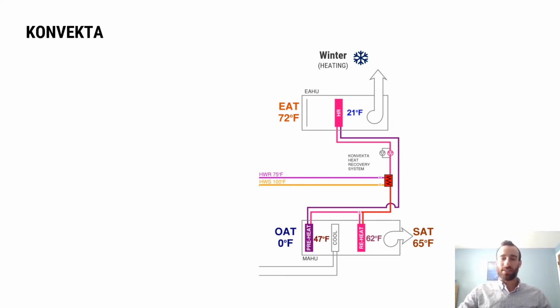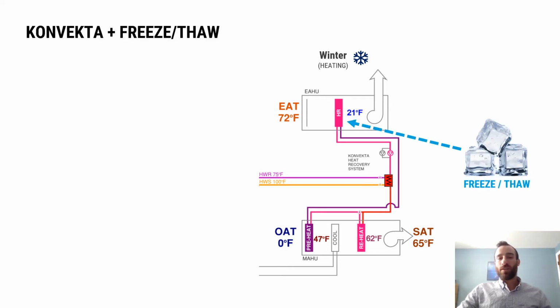recovery system. So this is an example of KONVEKTA, which is a glycol energy recovery system, probably the most efficient one on the market available today. One of the issues that plagues glycol energy recovery systems is that if you cool the exhaust too much, if you extract too much energy from the exhaust airstream, you actually start to freeze any humidity in that exhaust airstream, and the exhaust coil will block up into a big block of ice. But if you purposely freeze that exhaust coil and then thaw it again and really control that freeze and thaw cycle, that's when you remove that limitation.